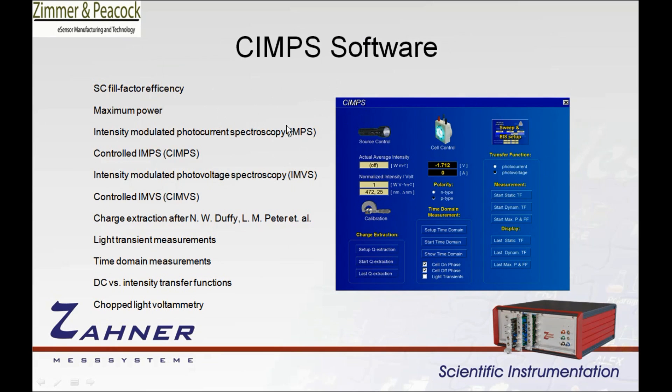With the software you can do solar cell fill factor efficiencies, maximum currents, and intensity modulated photocurrent spectroscopy. cIMPS is proprietary and is the controlled version of IMPS. You can also do intensity modulated photovoltage spectroscopy — controlled IMVS — charge extraction as defined by Laurie Peter from Bath, light transient measurements, time domain measurements, DC versus intensity transfer functions, and chopped light voltammetry.